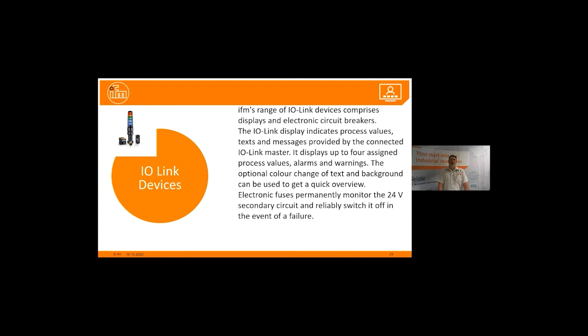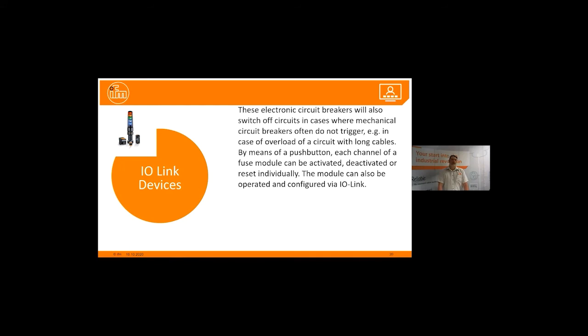Electronic fuses permanently monitor the 24-volt secondary circuit and reliably switch it off in the event of failure. These electronic circuit breakers will also switch off circuits in cases where mechanical circuit breakers often do not trigger, for example, if it's a long cable. By means of a push button, each channel of a fuse module can be activated and deactivated or reset individually. The module can also be operated and configured via IO-Link.